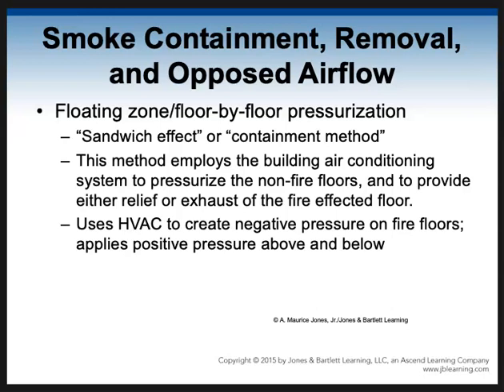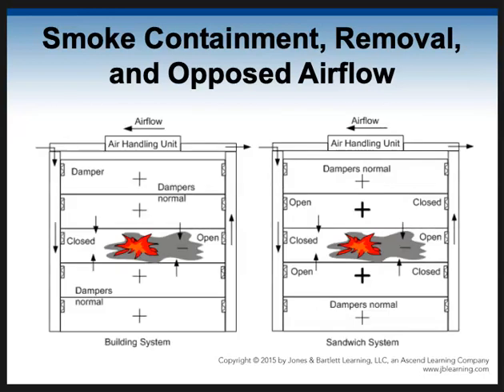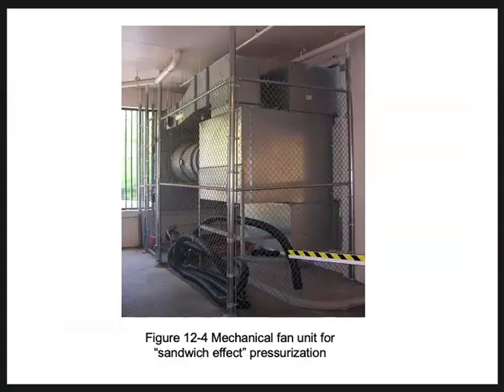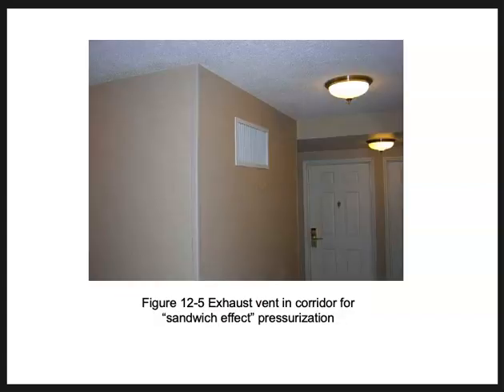Of course, this all has to be integrated with the alarm system. It's electrically controlled. So because fires take out the electricity, of course, it's going to have some kind of generator backup, to make sure it works even if the building's on fire. So here's that illustration, and you can see where the positives are positive pressure, where air's being pushed in. The negative is where air's being pulled out. So it's a push-pull effect which keeps the fire sandwiched and the smoke onto 1, 2, or 3 floors, but hopefully above and below, that smoke is not going into those other areas. So they do that with these big, huge mechanical fans and the vents where it pushes the air into the corridors to create this sandwich effect pressurization.